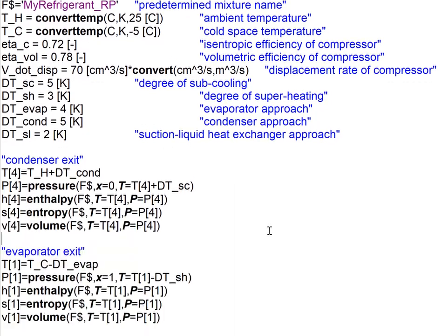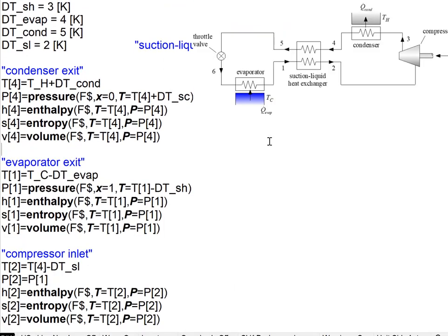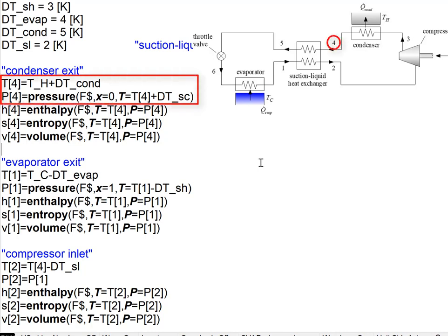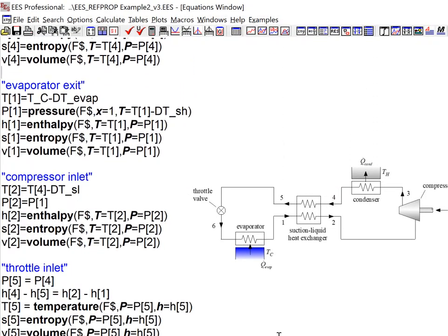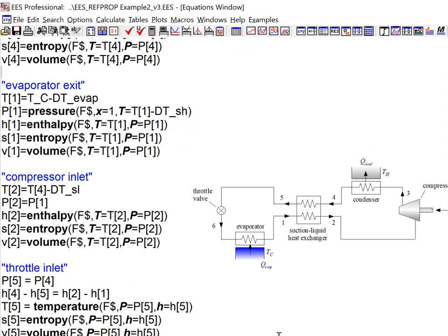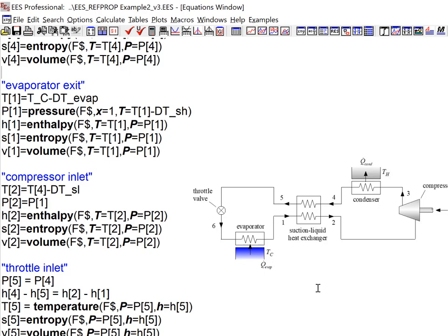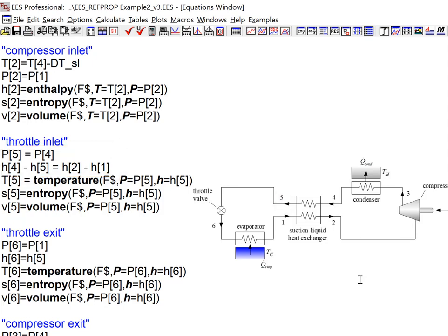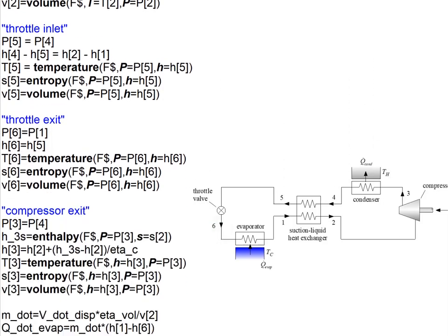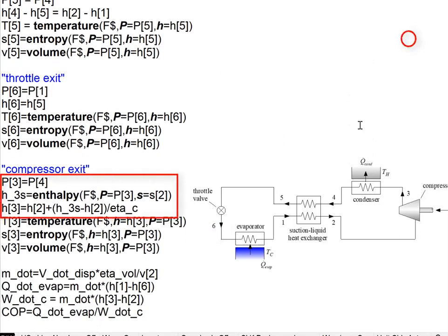The next step is to go through all the state points in the cycle. I'm just going to use MyRefrigerant_RP as the refrigerant, and I'll do this just like I would any built-in EES fluid. Working through the cycle, we have the condenser exit, which is specified by the approach temperature difference, and the degree of sub-cooling, and we have the compressor inlet, which is specified by the approach temperature difference of the suction liquid heat exchanger. Here we're assuming that the pressure remains constant on the high and the low sides. The throttle inlet, you get from an energy balance on the suction liquid heat exchanger that specifies the enthalpy, and you can get all the other properties. The throttle is assumed to be isenthalpic, so that gets you to state 6 here.